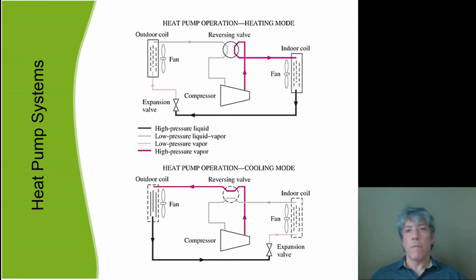They've traded functions. And of course, there's a few more things besides the reversing valve required to make the heat pump operate as well as the refrigeration unit, because you have to have controls for the reversing valve. Plus, it's more practical to have another expansion valve indoors and then one outdoors. So in most practical heat pump systems, there are two separate expansion valves, but that's a detail that doesn't matter for our consideration. So let's continue going through the heating mode of operation.